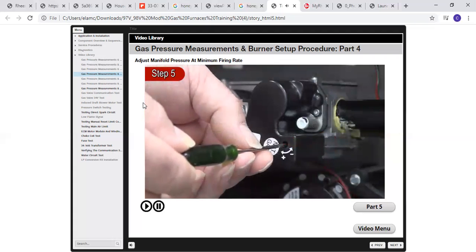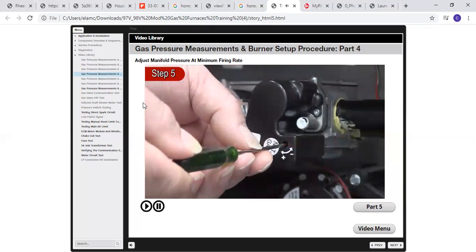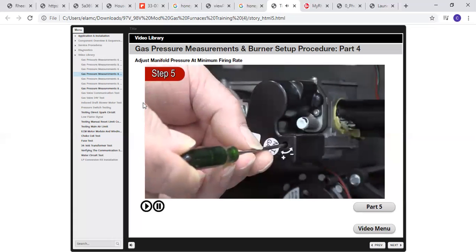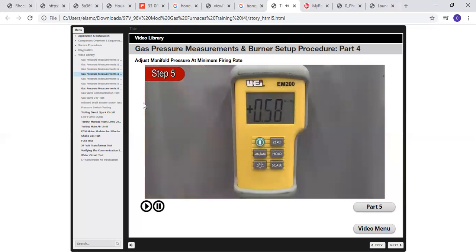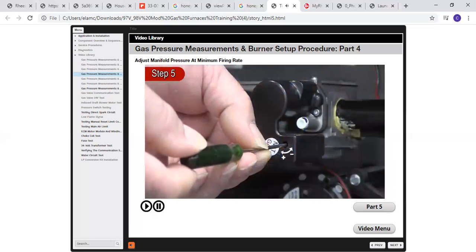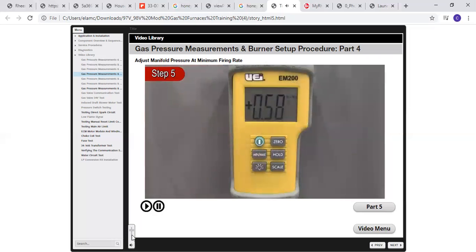The adjustment wheel will not stop rotating when the valve outlet pressure reaches its maximum or minimum value. Instead, the wheel can be rotated further, but no further adjustment to the outlet pressure will be made. Once at the maximum adjustment, high or low, the wheel can be turned in the opposite direction, and this will cause the pressure to also move in the opposite direction. The first click in the opposite direction will cause a pressure change in the opposite direction, even if the maximum adjustment in the original direction has been exceeded by several clicks.